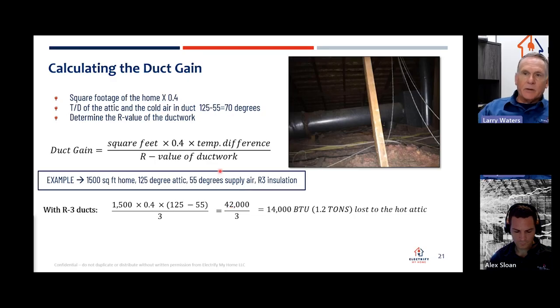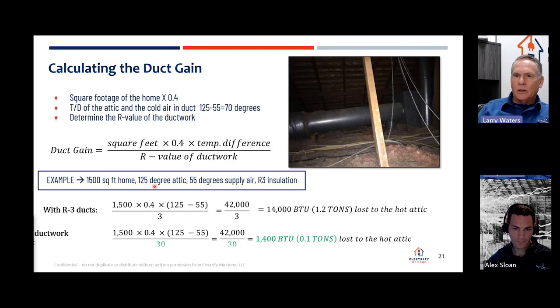Now, this is a very conservative number, again, because we have 125. Obviously, if we have R6 ductwork in the attic, this number is going to change. These numbers are going to be a little bit different. If we want to use a more accurate number and say, hey, on the hottest days of the year my attic is 140 degrees, you can do that measure as well. But this is a great way to communicate to the customer and to understand how much energy and how much capacity we're using just to keep these ducts neutral. So in this particular application, we're going to use 14,000 BTUs of cooling every hour to keep those ducts neutral. That's a lot of BTUs.